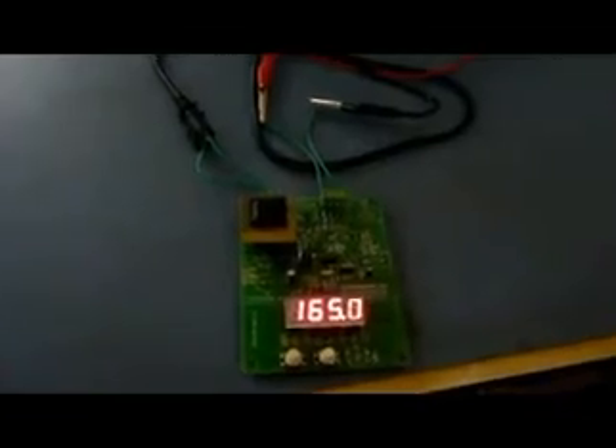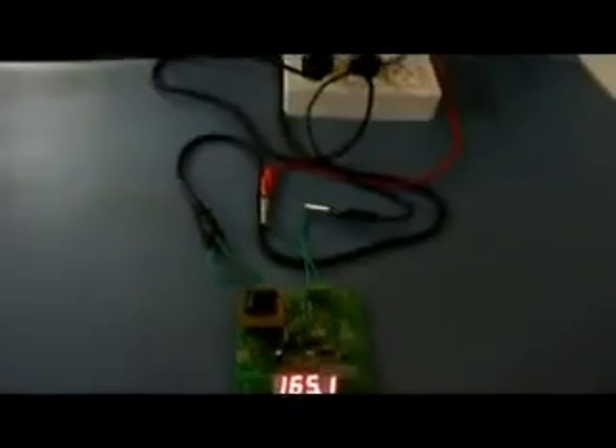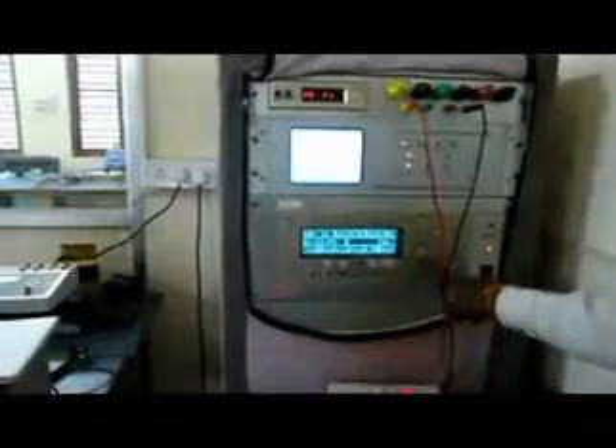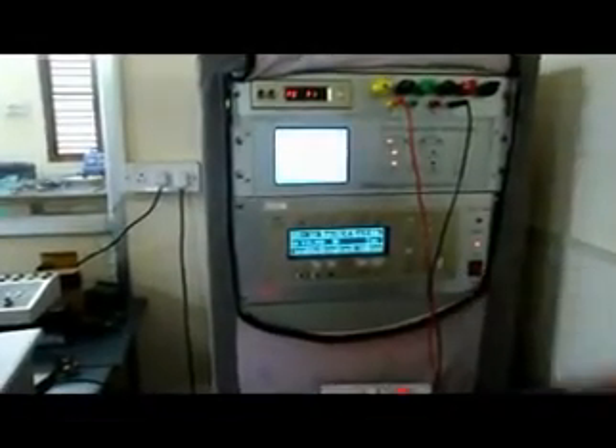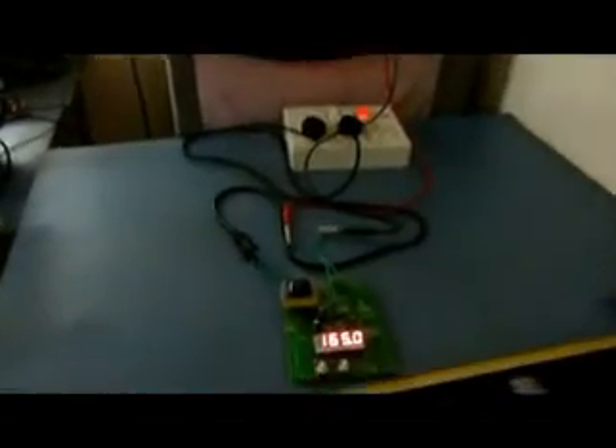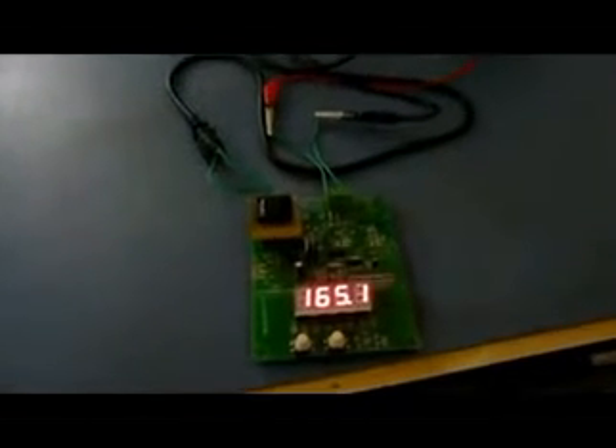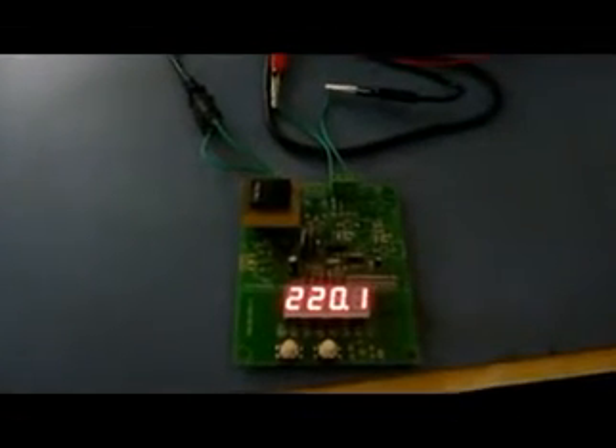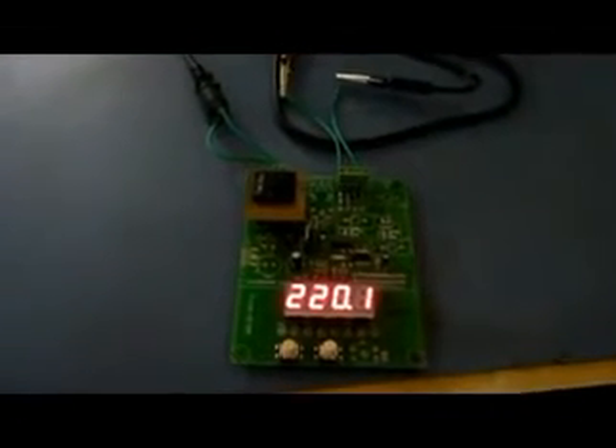We will move to the next point, that is 75%, 165.0. That is what 75% should give us. 50% of 220 volts, that's 110, and 75% is 165.0. We go to 100% for the next step. This should read 220 volts. So we have 220.1, and on the reference we have 220.071.